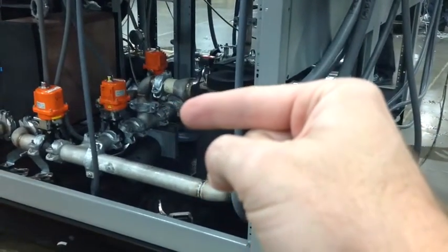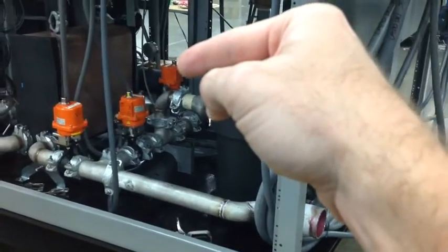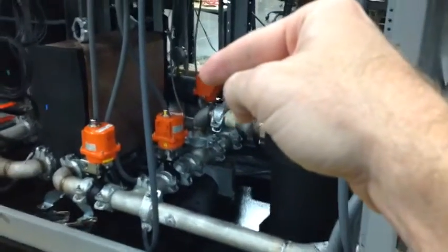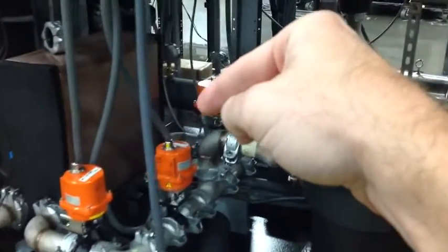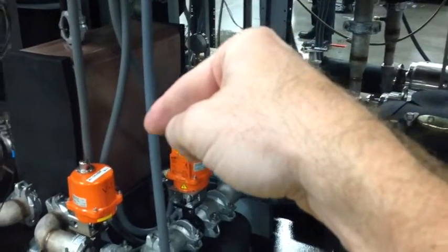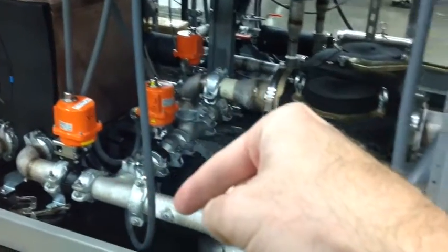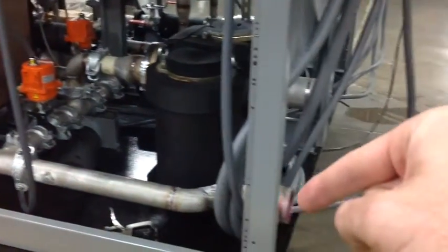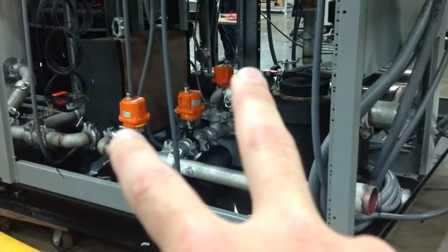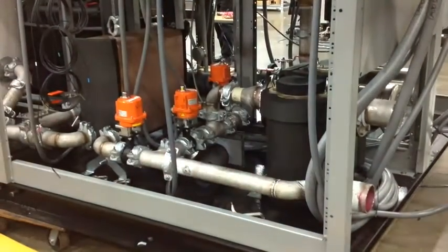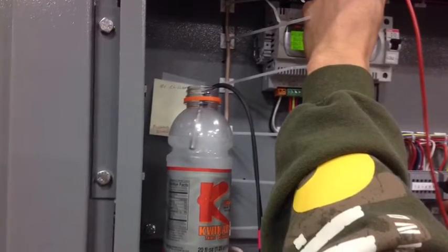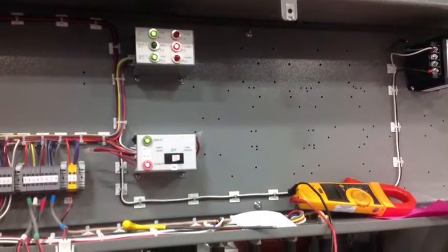If the bypass valve is closed, water will go around and, as I am showing, go through the heat exchanger, exit through valve 1 here, and then return to the building. In that final loop, it was providing cooling through the heat exchanger to the load. These 2 valves would be open in the load situation, and the middle valve would be closed. The middle valve opens and the other valves close in bypass.